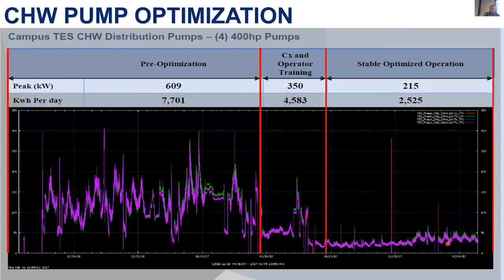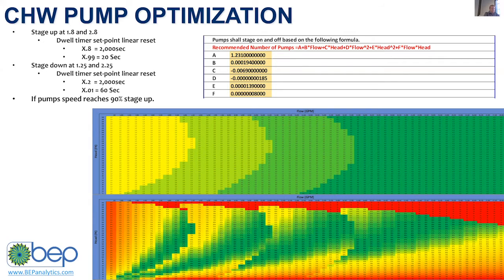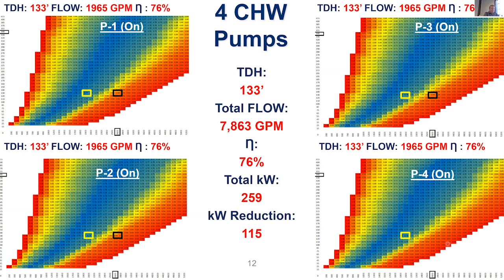What's really important here, there's an important takeaway. A lot of people see this presentation and say, okay, if I have pumps in parallel, I should turn all those pumps on. That's definitely not the right answer. If I turn on the 4th pump, and let's say I had a 5th pump and a 6th pump in this scenario, it's going to keep moving to the left of the curve, and I'm going to eventually get to another bad spot on the curve. So this is how simple the logic is that can accomplish this.